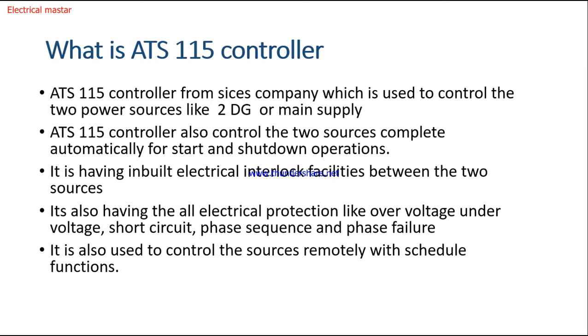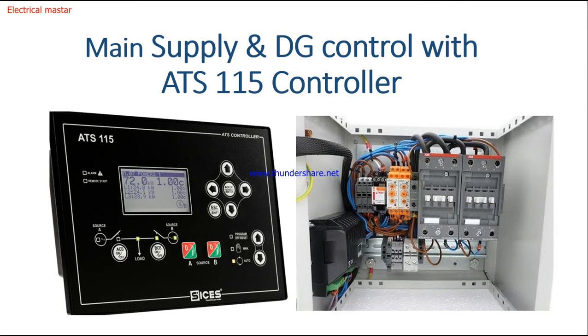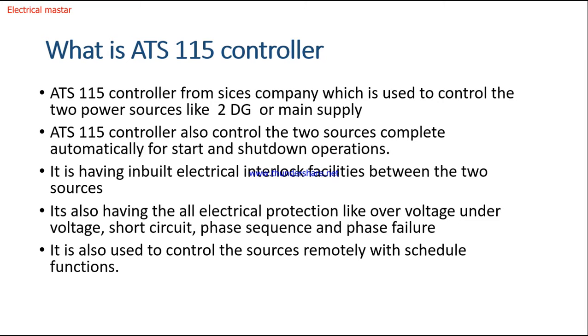It has inbuilt electrical interlock facilities between the two sources. This is a very major point. If you connect the two sources and close both at a time, there is a chance of flashover and a big short circuit issue. So this ATS has the inbuilt electrical interlock to avoid both the sources closing at a time. So we can avoid big problems.